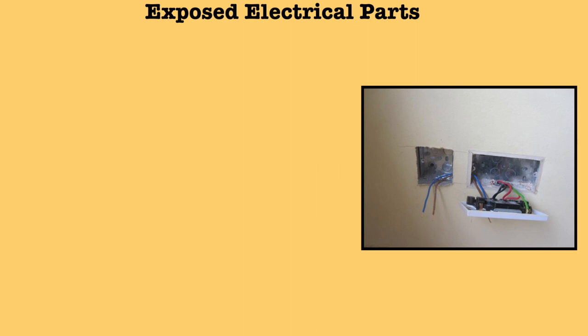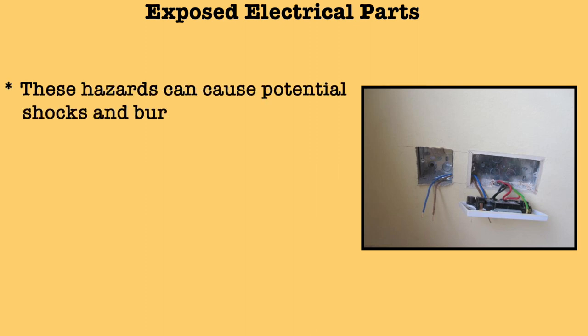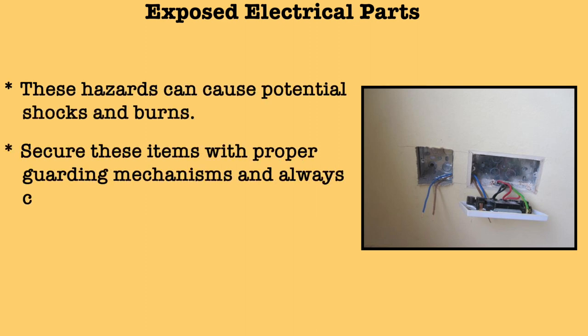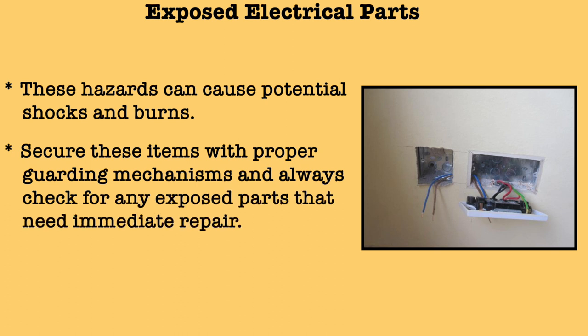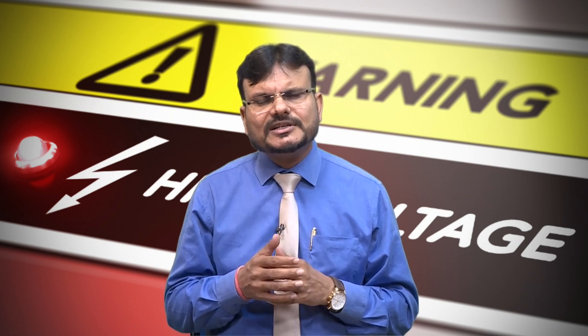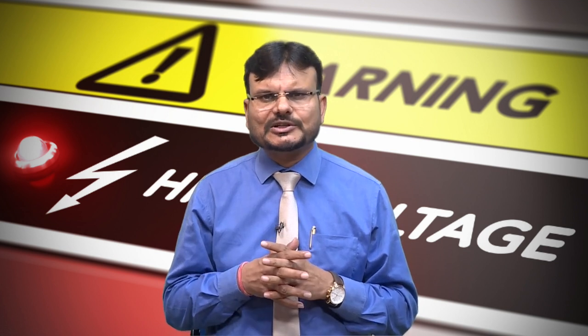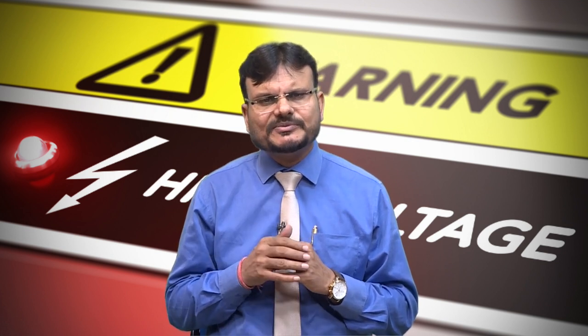Exposed electrical parts can cause potential shock and burns. Secure these items with proper guarding mechanisms and always check for any exposed parts that need immediate repair. Regarding improper grounding — the most common OSHA electrical violation is improper grounding of equipment. Proper grounding can eliminate unwanted voltage and reduce the risk of electrocution. Never remove the metallic ground pin, as it is responsible for returning unwanted voltage to the ground.